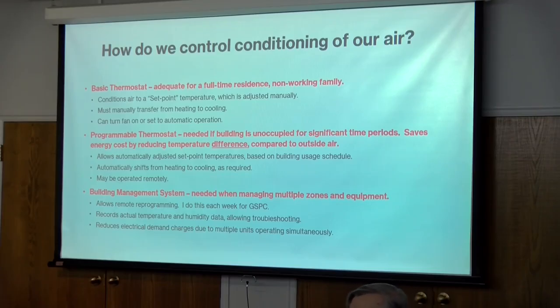The other advantage is that it allows us to reduce electrical demand charges. Electrical demand is something residents don't pay for, but all commercial facilities do. We can manage through the building management system which air conditioners come on at what time, and set a priority to avoid multiple air conditioners running in the same 15-minute period, which would add to our demand charges. It's another mechanism by which the church can reduce the charges from the electrical power company.